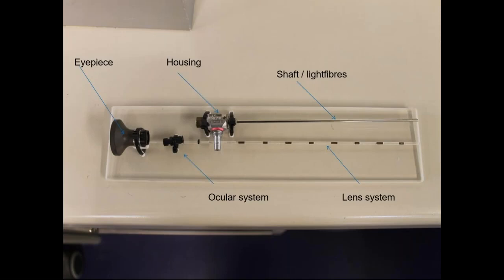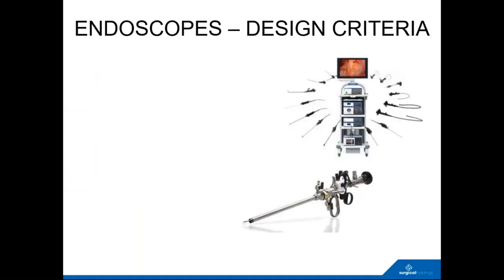And then nowadays there are also chip on tips, so this lens system is completely not there, and there's a chip basically at the tip, a CCD chip or a CMOS chip at the tip, which will take the image back via wires. So we'll talk about some of those later on when we talk about the number of different weird and wonderful scopes that are out there. So design criteria behind endoscopes, I mentioned there's a lot of them, and the reason there's a lot of them is that there's a lot of different uses for them, both diagnostic and therapeutic.